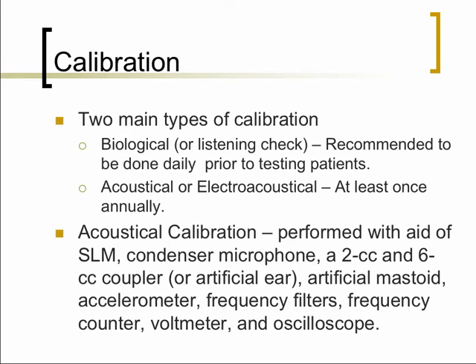And then you'd have other devices that you would employ when you're connecting the different transducers of your audiometer to the sound level meter. These devices include a 2cc coupler or a 6cc coupler. The 6cc coupler is also known as an artificial ear. You could use an artificial mastoid if you're doing bone conduction calibration. You would use an accelerometer again for bone conduction calibration. You might use some filters. You might use a frequency counter, a voltmeter, and an oscilloscope.